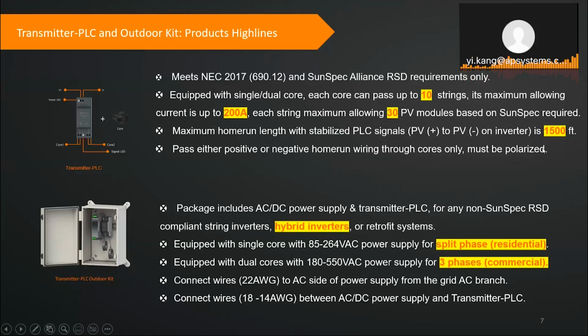And yeah, that's actually one of the things we've had happen as well. If you do have a SunSpec certified inverter, and then you also install a PLC transmitter kit, that's actually a negative thing. Don't install both. Make sure if your inverter is SunSpec certified then only use that one. And if it's not certified, then you need the PLC transmitter kit. Installing both will actually cause issues. So just keep an eye out on that, and if your inverter is SunSpec certified, do not buy this unit. Thank you. Correct. That's a good point.